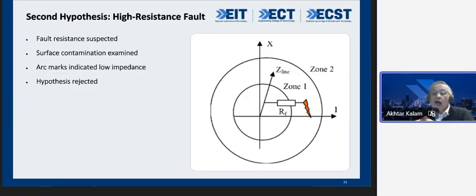So I think I solved the problem, because people said to me, it's a high resistance fault. High resistance fault. If you know, this is what is called zone 1 and zone 2. Because the fault resistance was high, it went to zone 2 and therefore did not operate in zone 1 time. So you think that the fault resistance is the problem. You think that there is contamination on the surface that you are examining, and that's a problem. You think that the arc mark indicated low impedance. You think all these things, and all your hypotheses have been rejected.